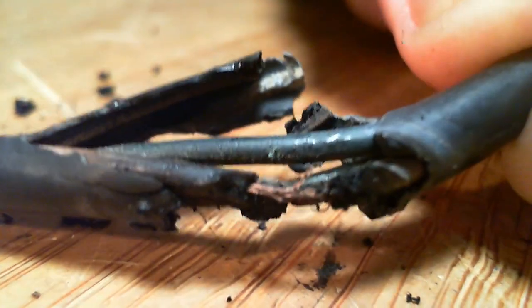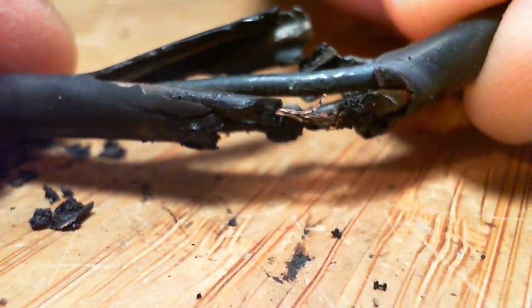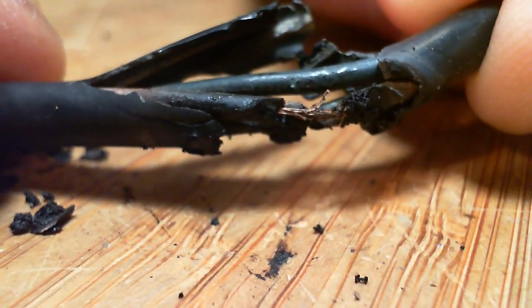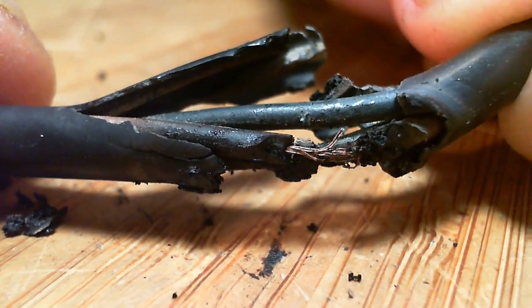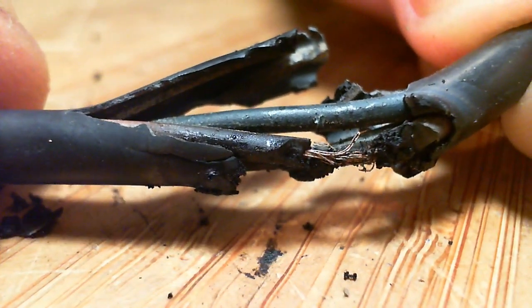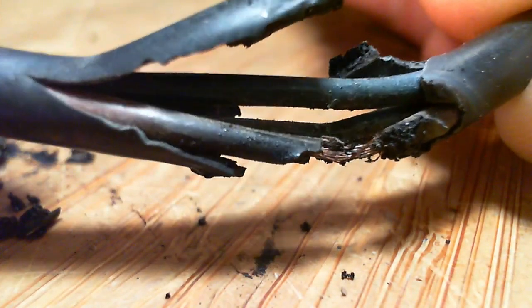The rest of the wire looks fine. I don't see anything. I've never, ever seen something like this. Never had a power wire fail like this. You see the color of the copper. If it's hot, it can change color. I don't see any color change in it.